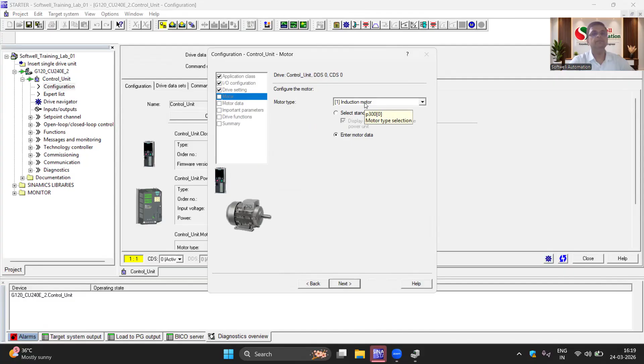Next step relates to the type of motor: parameter P300, and the motor type is induction motor. Next is the motor terminal connection, star or delta, parameter P133. Right now the motor connection terminal is star, so we select star.